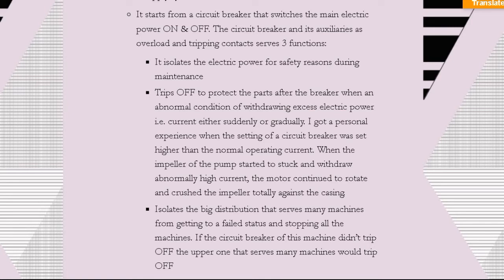We had one example previously during work, where someone tuned the protection to the full current of the motor while the load was very small. So when the pump was jammed, the pump was completely damaged and was not protected by the circuit breaker, because the motor was rated higher than the pump itself.